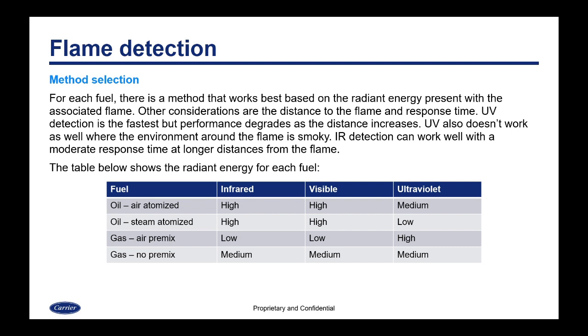For each fuel there's going to be a method that works best based upon the radiant energy present with the associated flame. Other considerations are distance to the flame and response time required. UV detection is the fastest but performance degrades as the distance from the flame increases, and UV also doesn't work as well where the environment is smoky. IR detection can work well with a moderate response time at longer distances. In this table, with air atomized oil you're going to have more infrared radiation than ultraviolet. With steam atomized oil you will have more infrared and much less ultraviolet — most likely because steam atomization creates a smokier environment. Gas with an air premix is low on infrared but high on ultraviolet; gas with no premix is about medium on both, so either would work equally well.